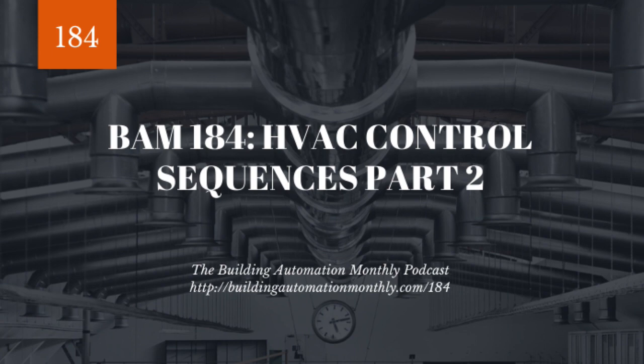In air handling systems like air handlers, especially VAV air handlers, the air will be delivered via the ductwork to a VAV box, which then will regulate it even more. Now we're going to come back to that because there's some important things that have to happen in order for that to work. But before we do that, let's go through a fan coil.